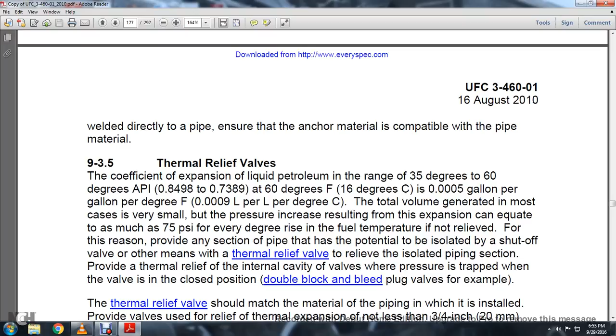For this reason, provide a thermal relief valve in any section of the pipe that has the potential to be isolated by a shut-off valve or other means, to relieve the isolated piping section. Provide a thermal relief valve in the internal cavity of the valve where the pressure is trapped when the valve is in the closed position, double block and bleed plug valves, for example.